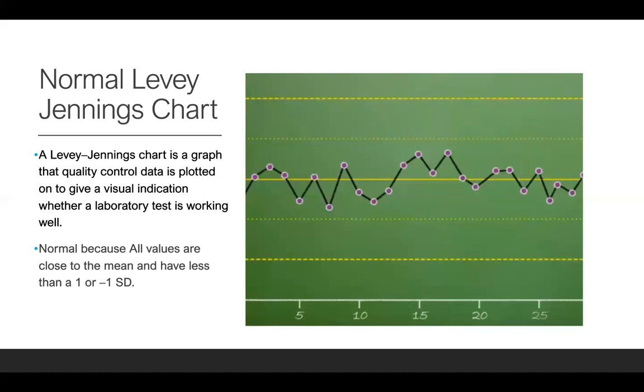So the first line above our solid mean line, the light dotted line, is going to be +1 SD, so +1 standard deviation. And the line above that one is going to be +2 standard deviation. Going down under our mean line is going to be -1 standard deviation. And going down below that is -2 standard deviation. This is a normal Levy-Jennings chart. We know that because all of our plots on the chart are within +1 and -1 standard deviation. They're all close to the mean. So we know that they're all within the same average and they are all accurate.